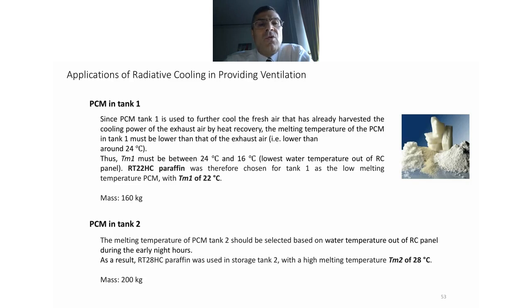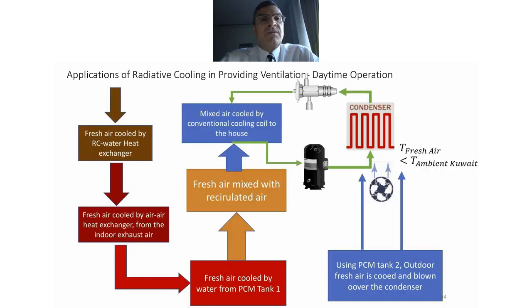And PCM2, we make it 28 because the air going over the condenser, we do not want it to be a very cold temperature. So this is more about the design of the PCM1 and PCM2, which is very important to be designed properly, and is in the paper. But basically, we need a mass of about 160 kilogram of these spheres, and 200 for the PCM2. It depends on the sizes, and of course on the temperature and the storing temperatures.